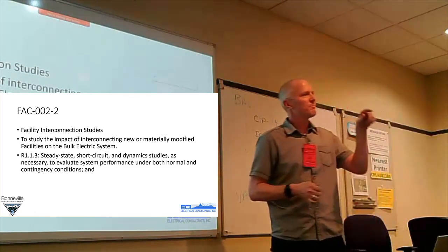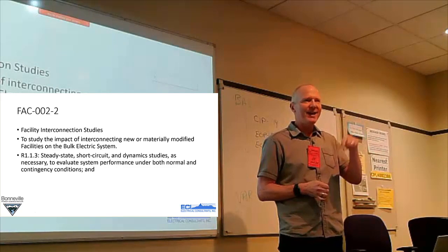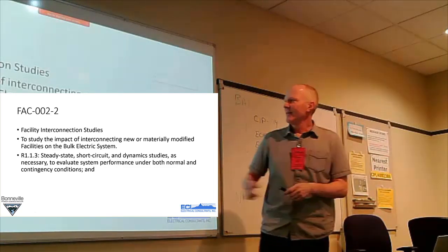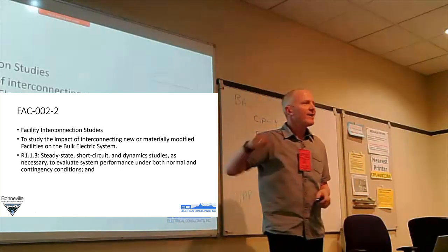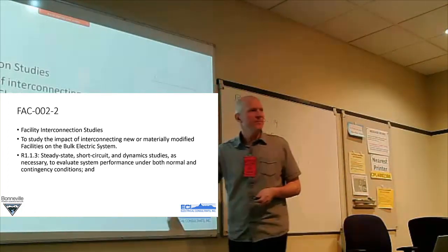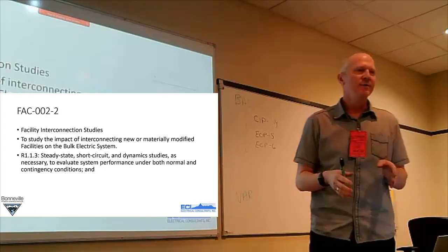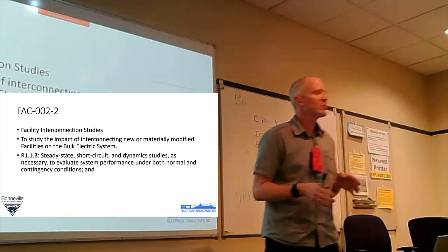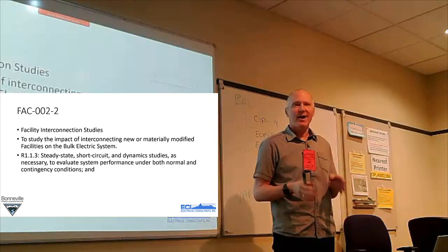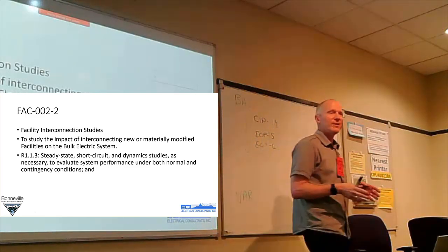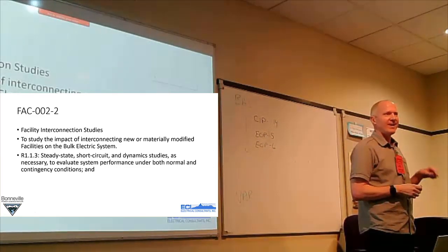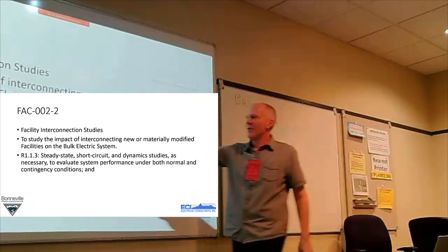But from a specifically transmission planning perspective, this is what we remind people of when we're going out and helping them study. FAC-002 studies protect you. Remember, a FAC-002 study requires all this stuff, all of it. And I think there's a good reason for it, because if you do a project in January and you do some lame study, which happens all the time, your planner who's doing the annual planning assessment is going to find your errors at the end of the year, because the annual planning assessment has all this stuff in it.